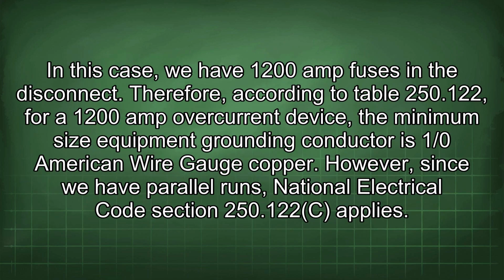250.122, which bases the size on the rating of the overcurrent protection device protecting the circuit. In this case, we have 1200 amp fuses in the disconnect. Therefore, according to table 250.122, for a 1200 amp overcurrent device, the minimum size equipment grounding conductor is 1/0 American wire gauge copper.